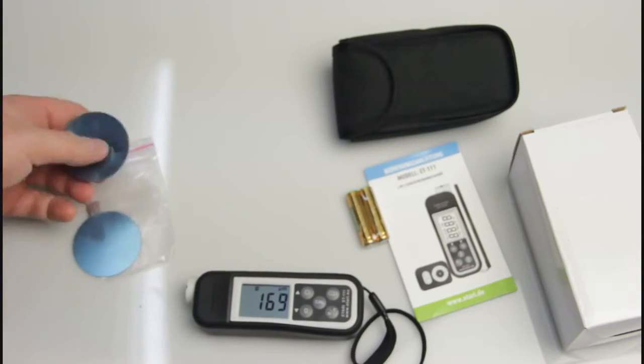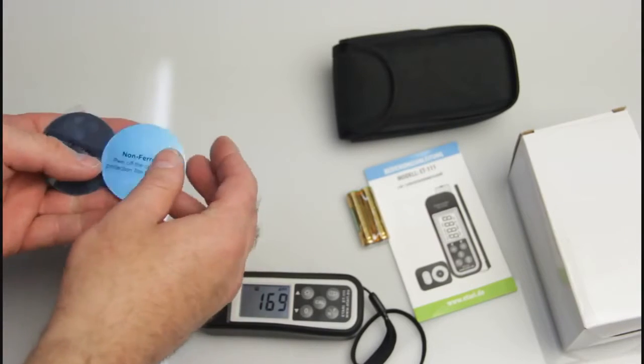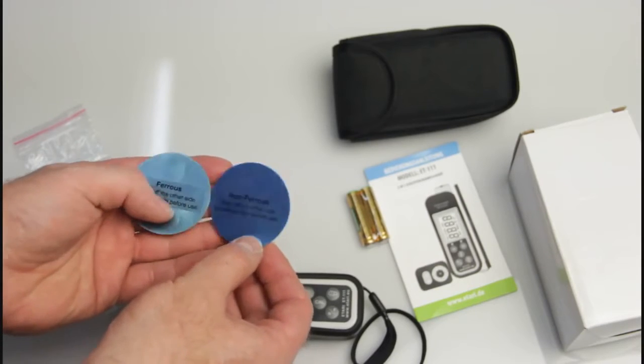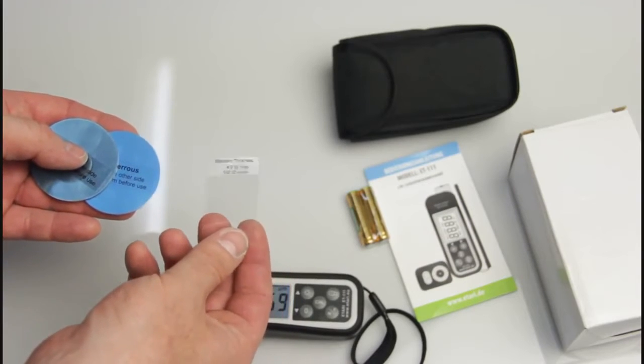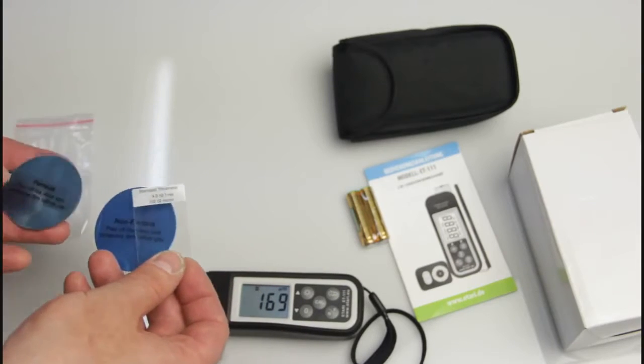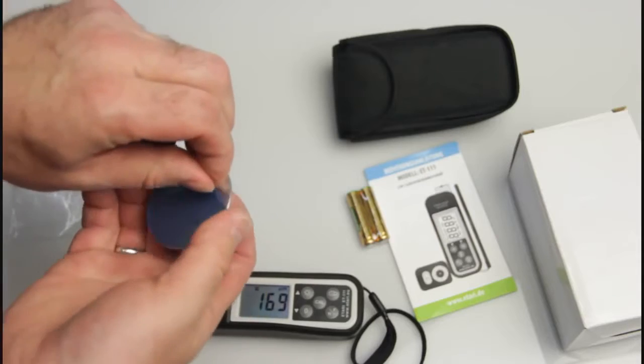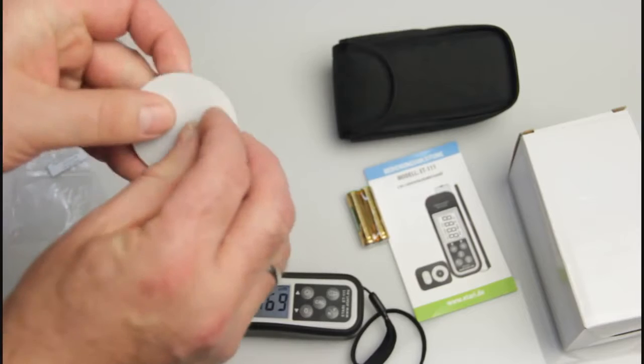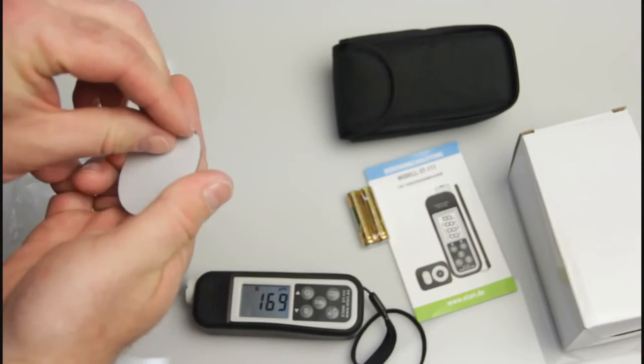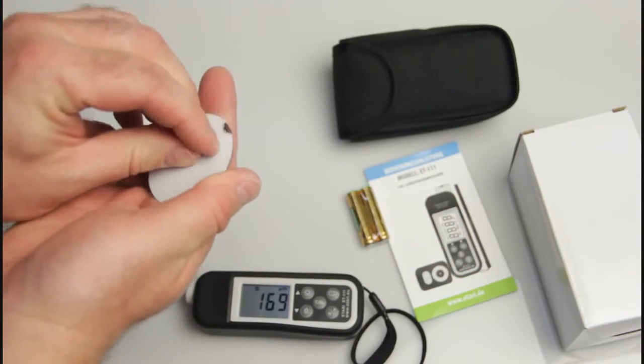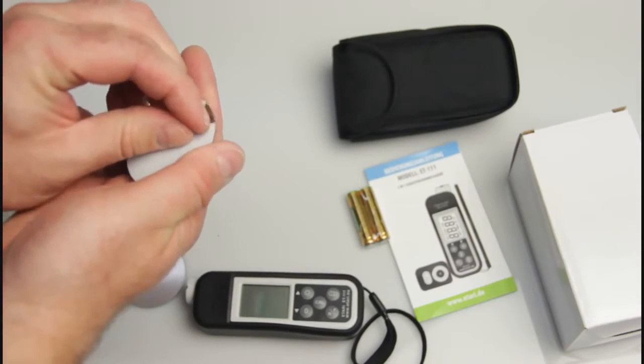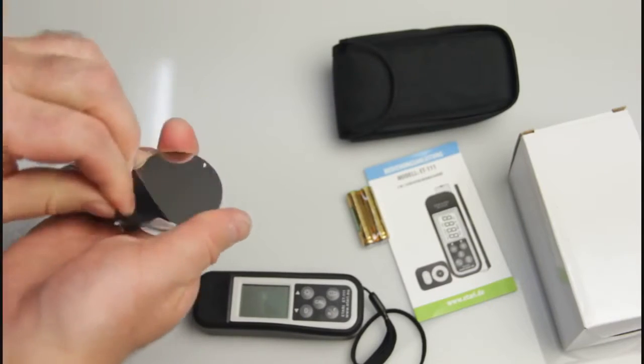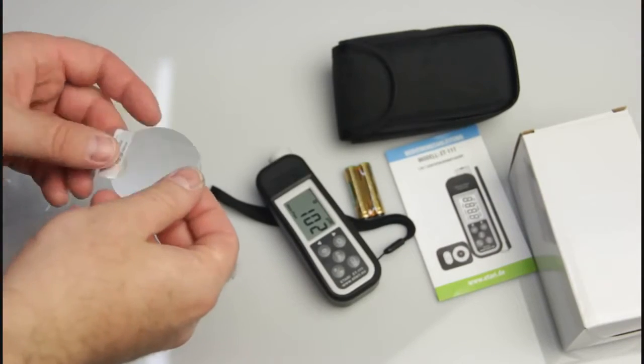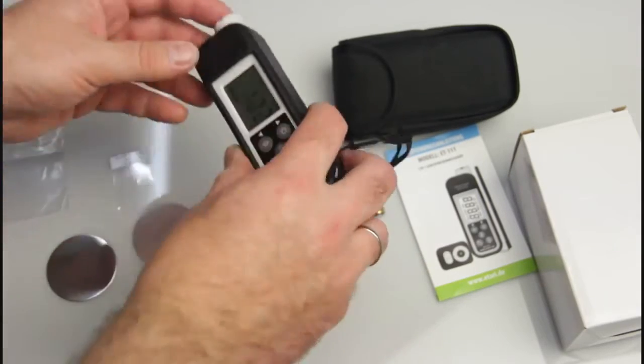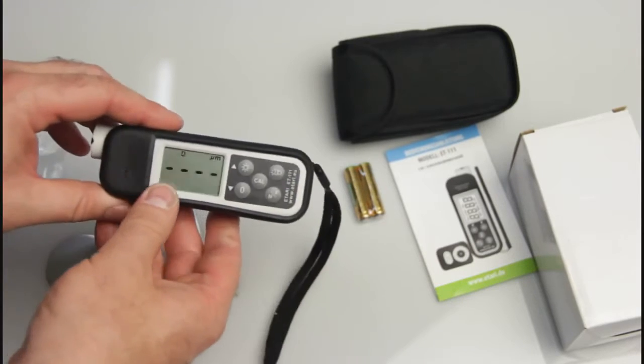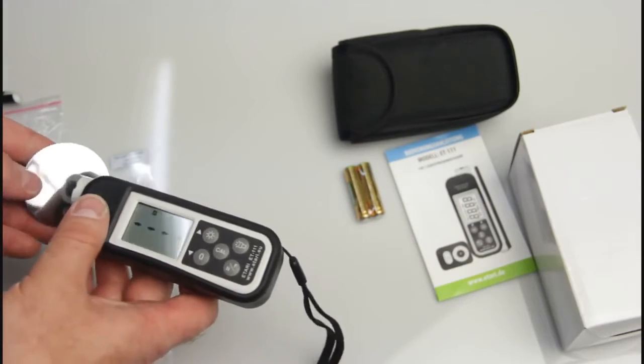How to do it? As we saw, we have a calibration set here. It has ferrous and non-ferrous metal plates and one plastic plate with a thickness of 102 microns, as we see. First of all, we have to peel off the protective sleeve from the metal plates. If you want, you can leave it on and calibrate right on this protective sleeve, but your gauge will not be accurate. Do not forget to do it the first time. Okay, when you have peeled off the protective sleeve, turn on the gauge, check for automatic mode, and let's calibrate it for the first time.